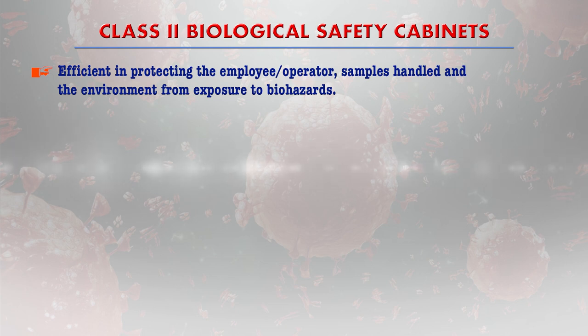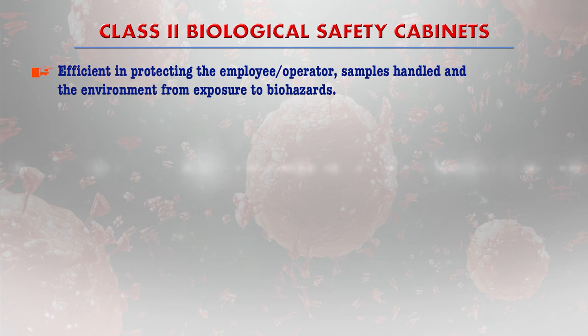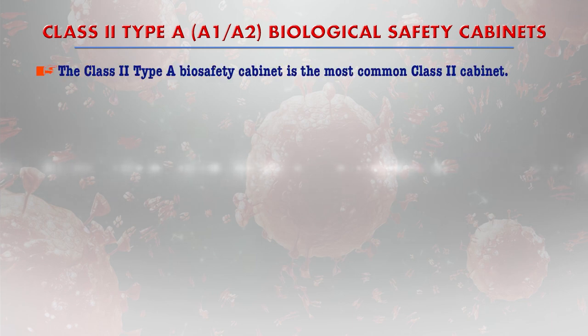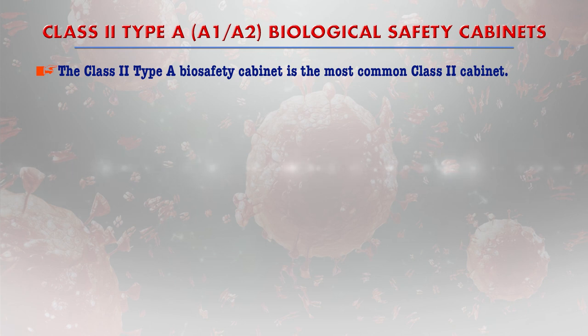Class 2 cabinets are highly efficient in protecting the employee and operator, keeping samples contamination-free, and protecting the environment from biohazardous materials. These cabinets are also suitable for work with microbial agents assigned to biosafety levels 1, 2, and 3. Class 2 type A biosafety cabinets are the most common class 2 cabinet, with a common plenum from which 30% of the air is exhausted and 70% is recirculated to the work area as downflow.